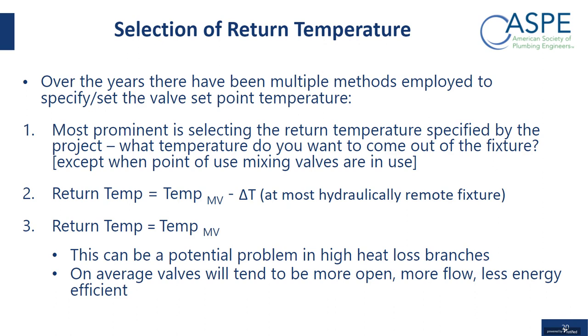So now once you've decided you want to use the thermostatic balancing valve, again, one of the main things is to select the return temperature. And I've seen different ways employed in how people select the return temperature. I would say the most prominent and the easiest one is if you know what the desired return temperature is. So if somebody says, I want 115 coming out of the fixture, then you would select or adjust the thermostatic balancing valve to 115. Now, that is assuming that there is no point of use mixing valves.